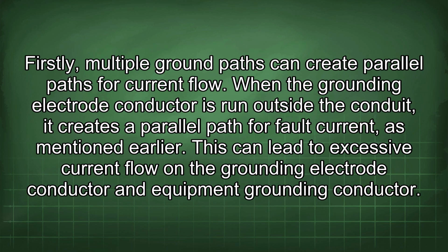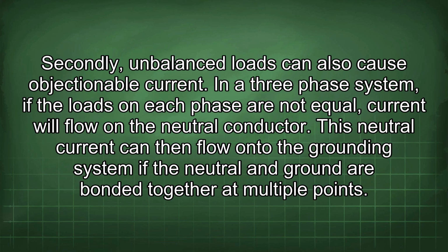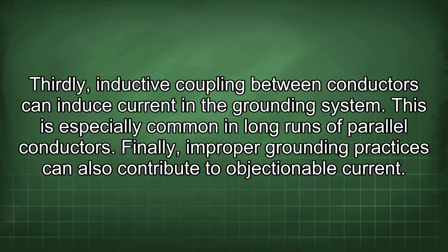Firstly, multiple ground paths can create parallel paths for current flow. When the grounding electrode conductor is run outside the conduit, it creates a parallel path for fault current, as mentioned earlier. This can lead to excessive current flow on the grounding electrode conductor and equipment grounding conductor. Secondly, unbalanced loads can also cause objectionable current. In a three-phase system, if the loads on each phase are not equal, current will flow on the neutral conductor. This neutral current can then flow onto the grounding system if the neutral and ground are bonded together at multiple points. Thirdly, inductive coupling between conductors can induce current in the grounding system.